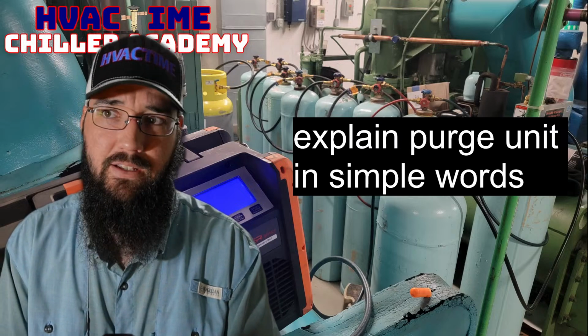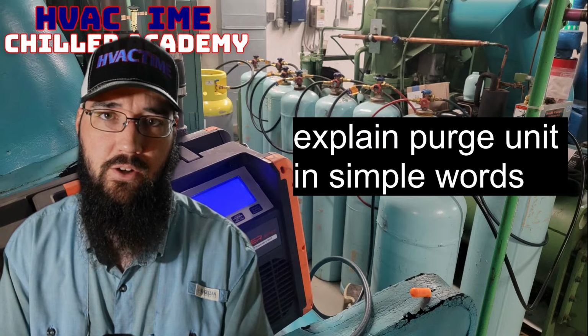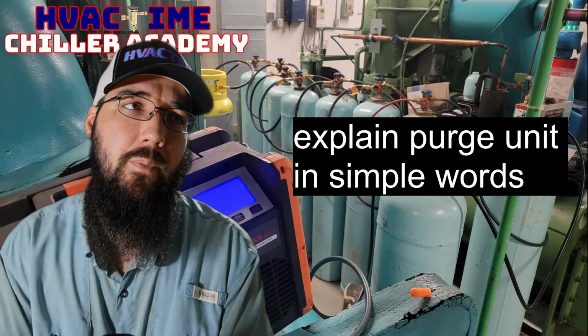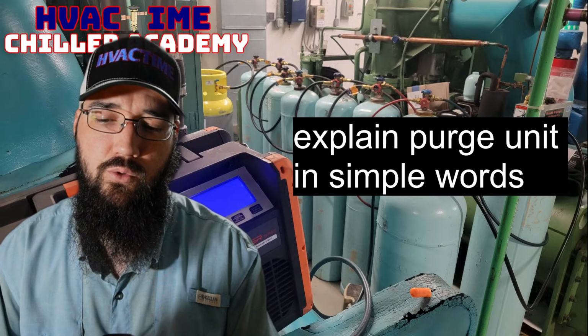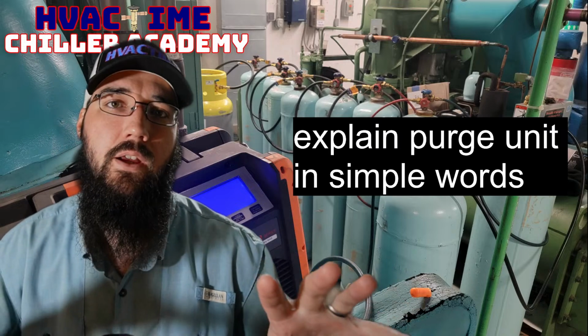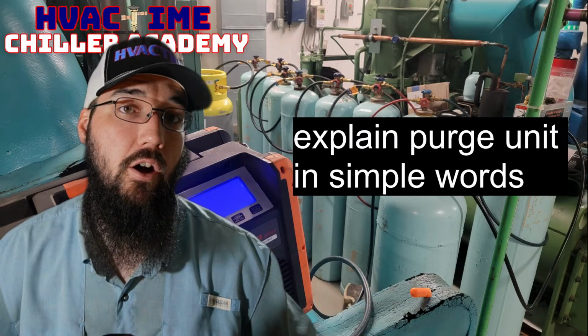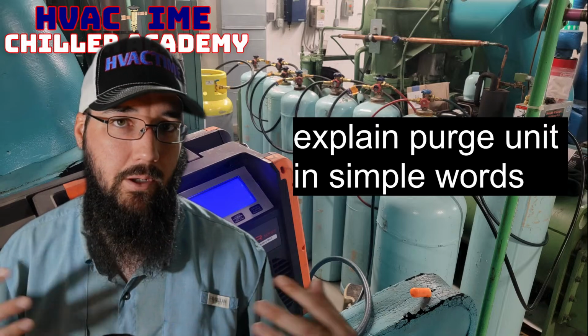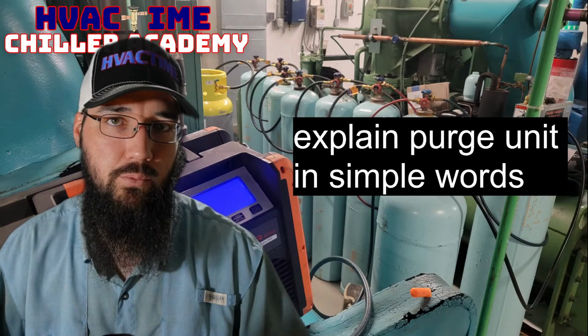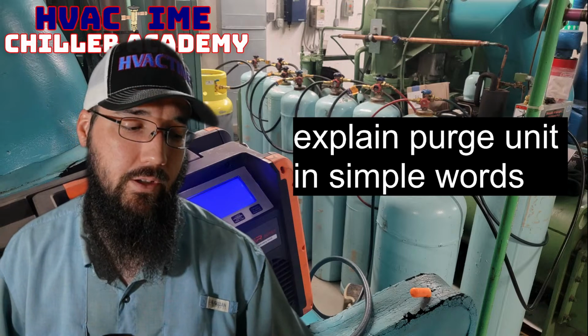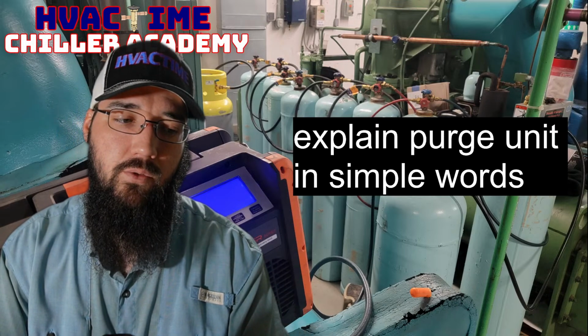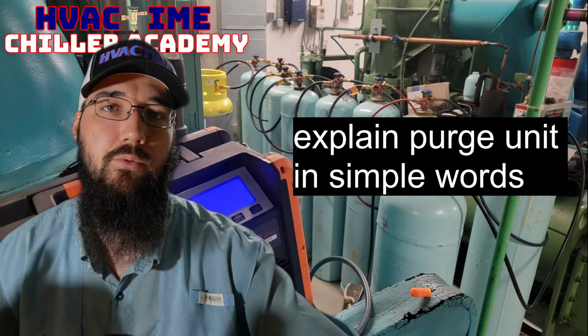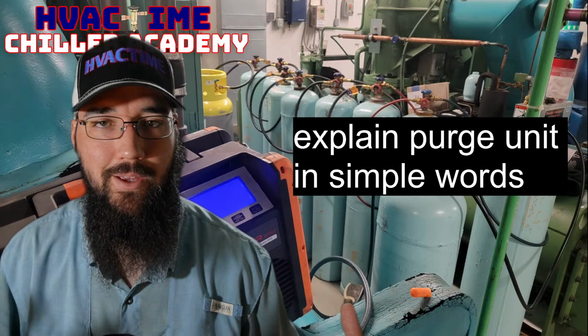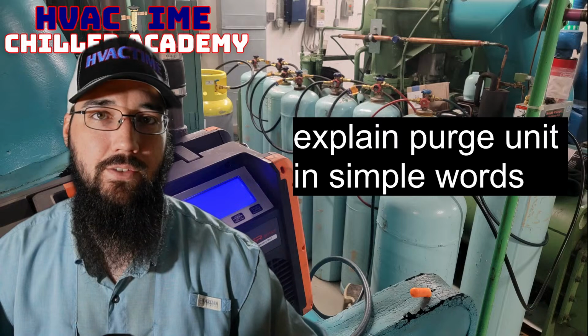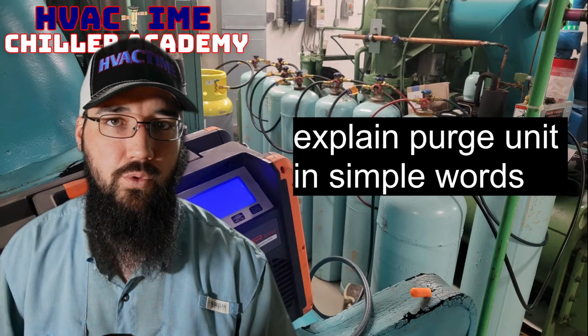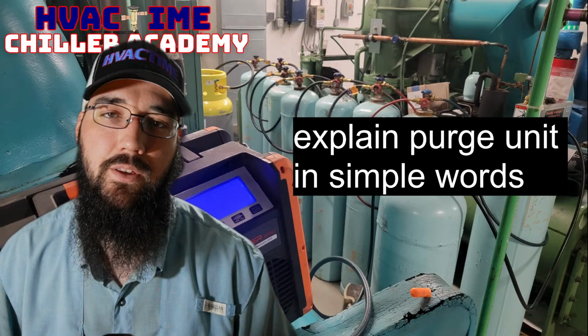And at one time, it was a fairly standard practice, because in many parts of the world these centrifugals will go through a shutdown period and they'll be off for months at a time. Not everywhere. In my particular region, we don't have much downtime. We run just about year round, and in some applications, genuinely year round. So we just never see those off cycles. But there are a lot of northern or upper parts of the hemispheres that do have pretty heavy shutdown cycles. During that time, those purge units aren't really going to keep up with non-condensables in the system, not the way that they need to.